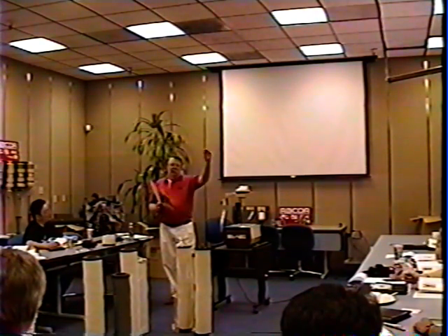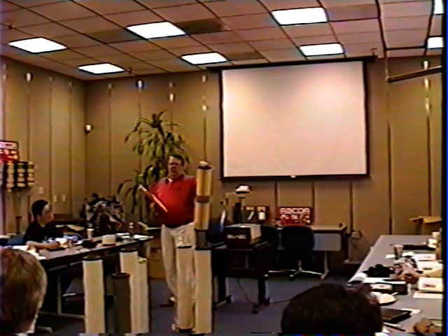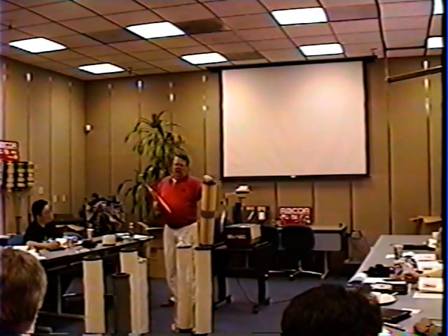In Brazil, we found out at the airport terminal that they were changing pre-filters about every 4 weeks. Here in the U.S. at the airport, they change them maybe 3 times a year. Now, if they got their jet fuel from Venezuela, which they do in some cases, they were changing pre-filters every 4 or 5 days. That's how bad it is.